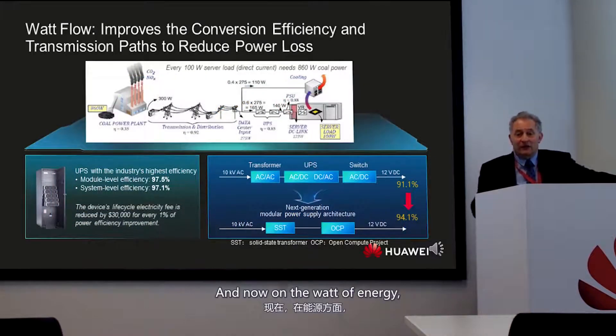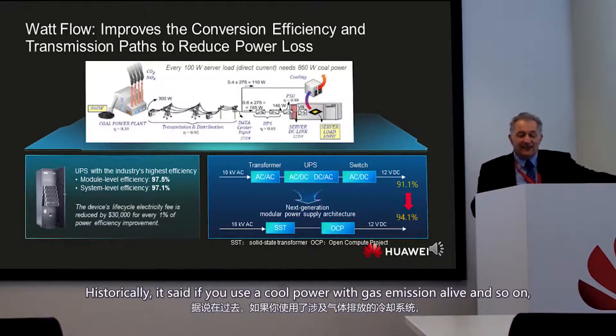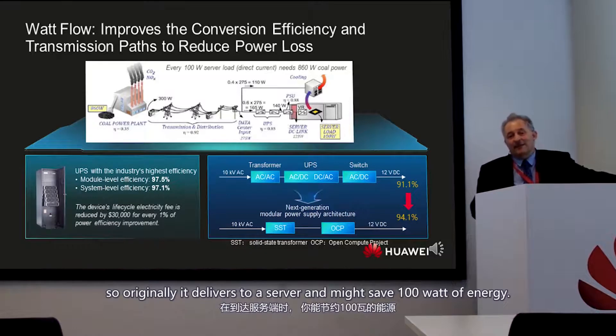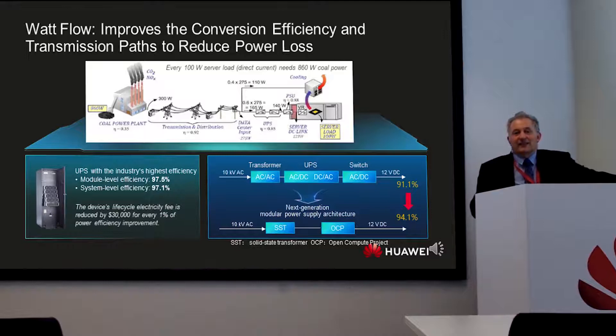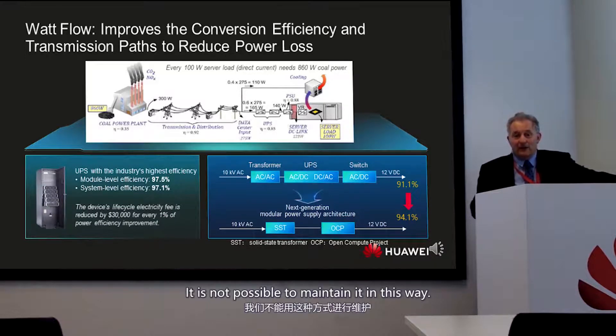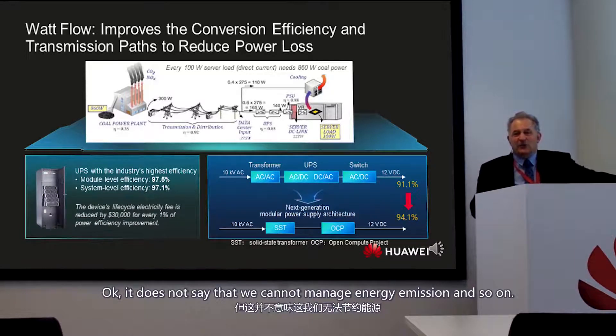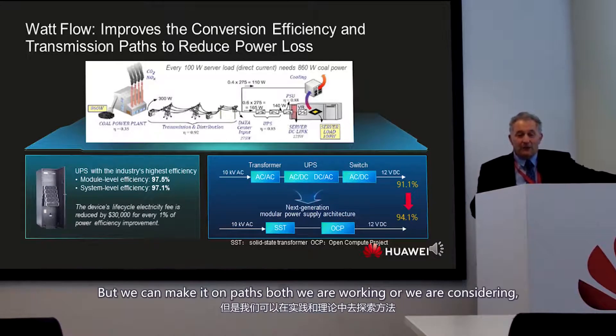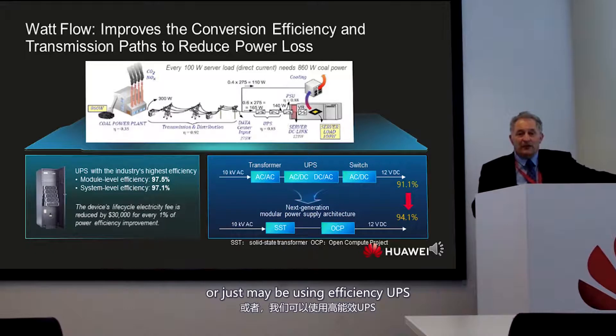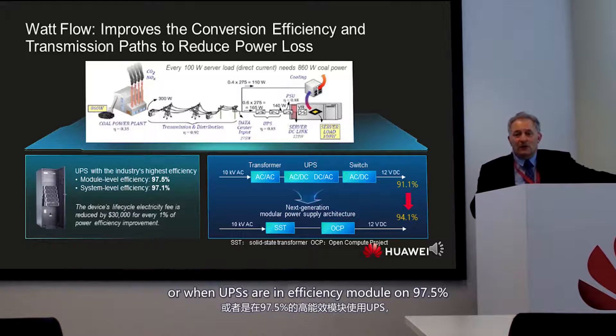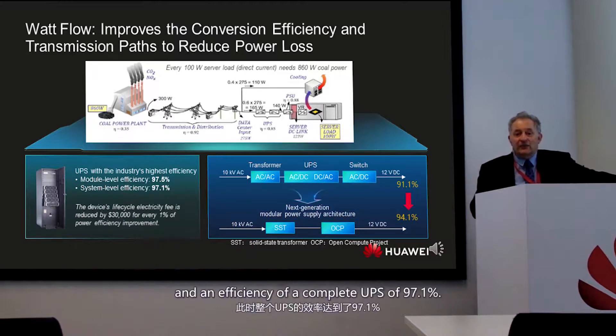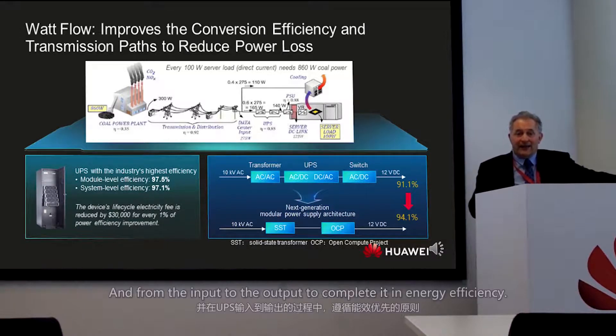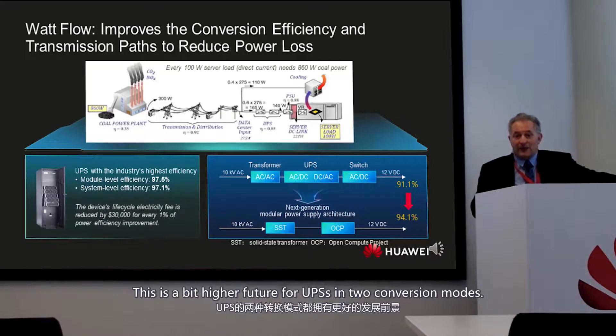How can we reduce energy waste? Historically, starting from grid power through transmission lines, we generate 800 Watts but only 100 Watts arrives at the server — all the rest is lost. In a data center we can address the last part of the chain by using a high-efficiency UPS with a module efficiency of 97.8% and a complete UPS efficiency of 97.1% in dual conversion mode.